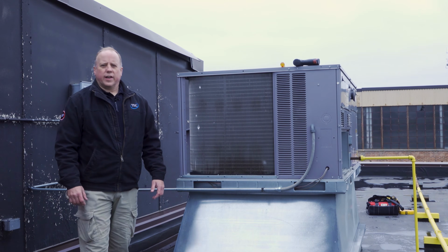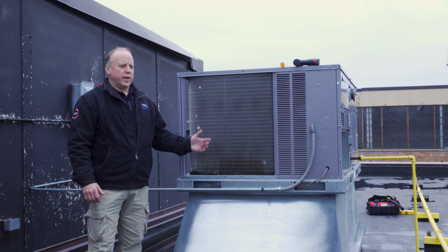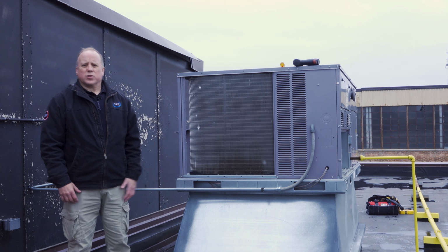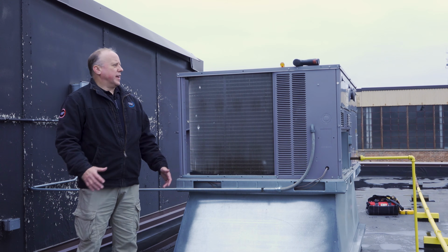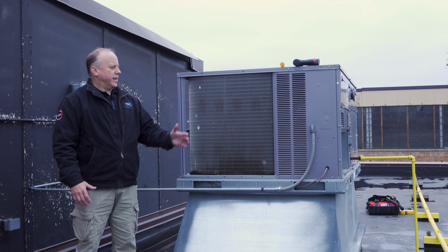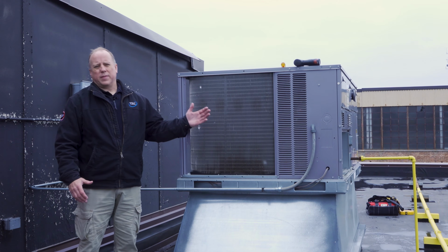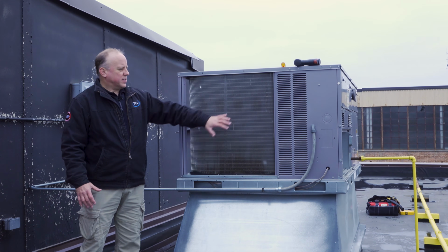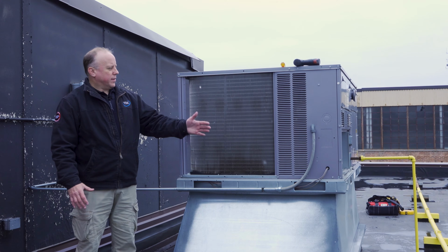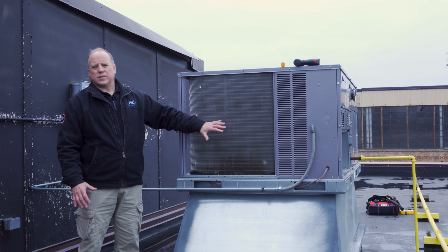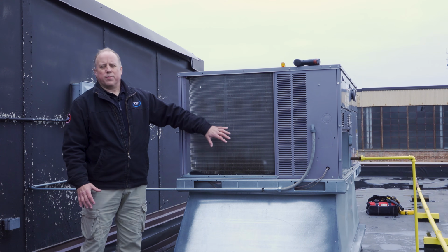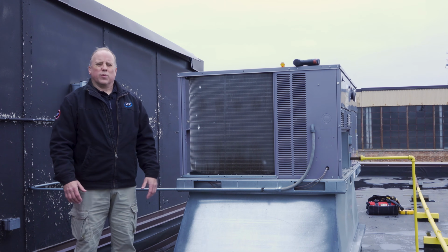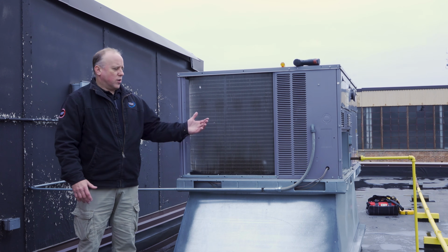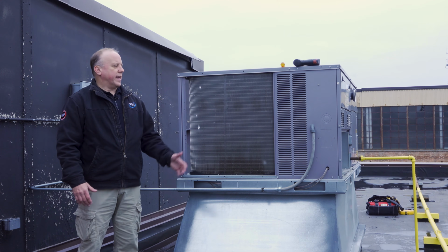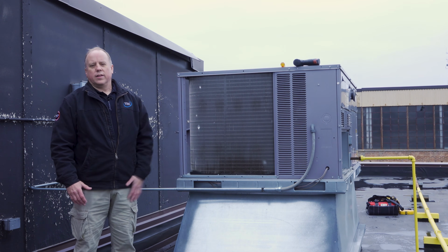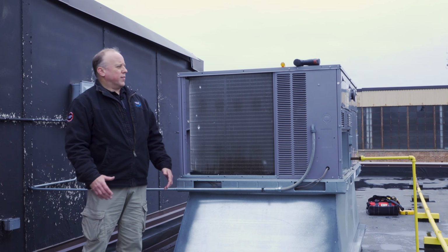So we're looking for more reasonable temperatures for comfort, cooling, and heating. We're going to go over coil cleaning now on the rooftop unit, starting with the condenser coil. When cleaning the condenser coil, we don't want to clean from the outside in, we want to clean from the inside out. We don't want anything sitting on the outside of this coil getting embedded inside, getting stuck there to a point where it may not want to come out at all, which will affect the operation of the unit and cause pressure issues down the road. So we want to get everything pushed out of the coil and get it as clean as possible. There are some different ways to do that.